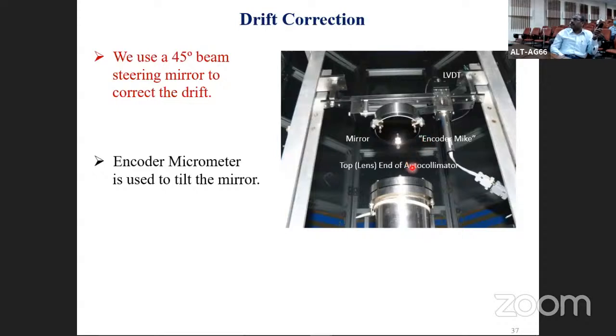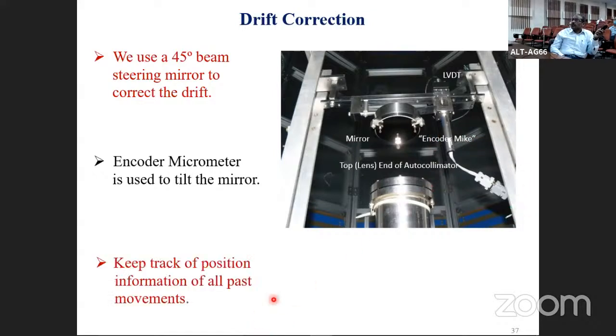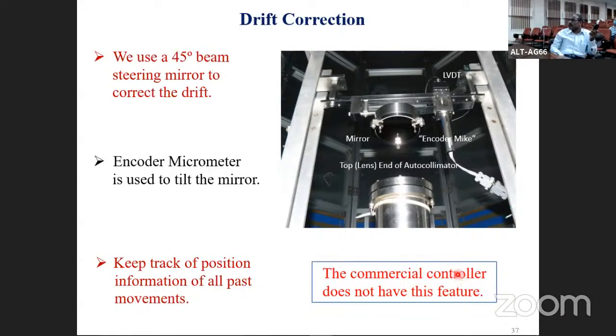Looking at the drift rate, we can predict also this is time dependent drift, and of course drift introduced because of our calibration process. So we want to keep track of this, of how much drift we are correcting as it's day to day, so that one knows, we can do a prediction that after so many days or weeks, one has to go and correct for this much drift. The commercial controller that we have doesn't have this feature, you don't have any memory. You just lose everything the moment you switch off. And we could not find anything in the market, so we decided to develop our own controller.